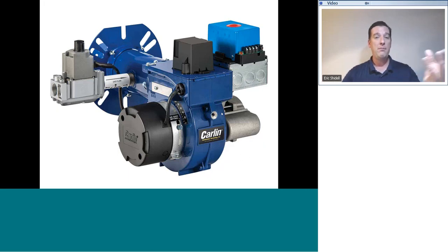If we get too much fuel and not enough air, the combustion products are going to go in a certain direction. If we get too much air and not enough fuel, the combustion products will move in the opposite direction. Levels of carbon monoxide and carbon dioxide and excess air will all change, and that can be measured by the combustion analyzer looking at those products of combustion. So, power burner. Any questions on power burners before we move along? And we got a couple extra pictures of some big ones. There's a big one.